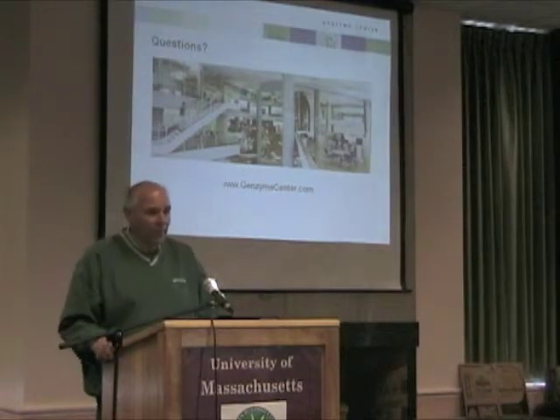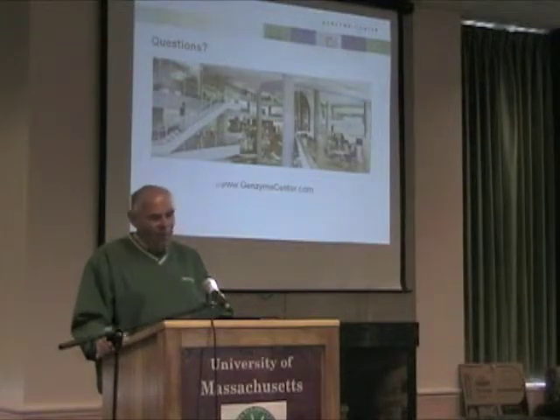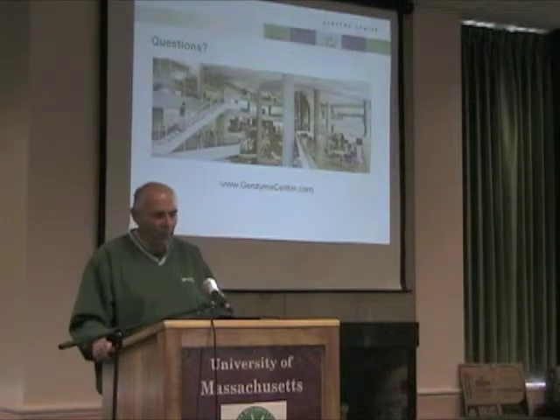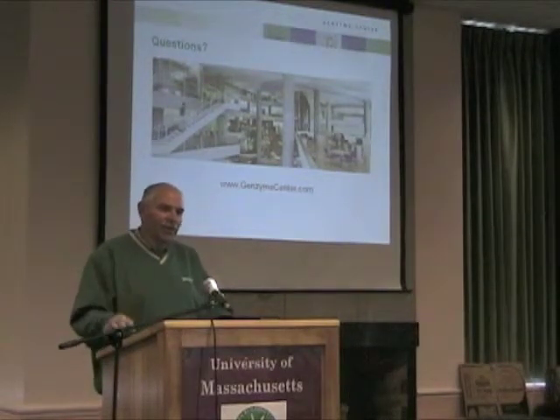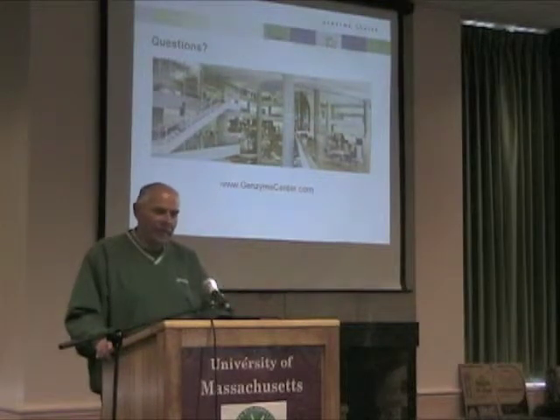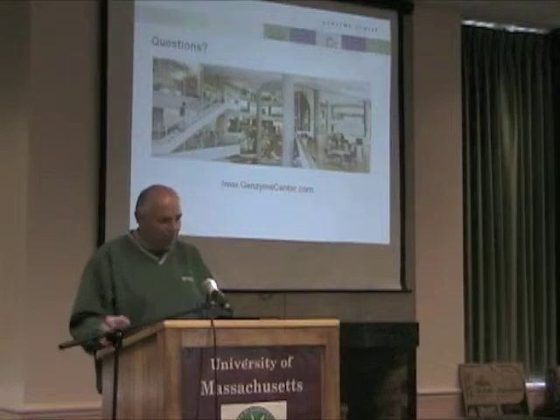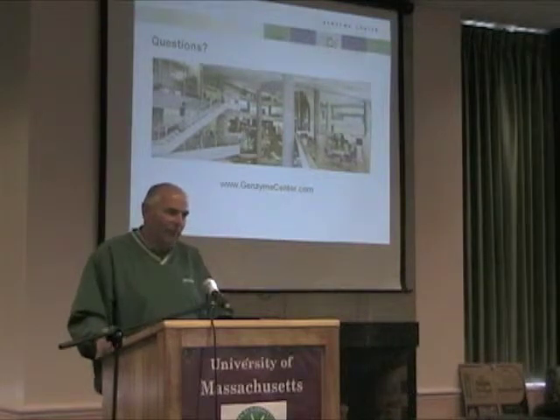I said, well, it's a platinum building. What can you save? We gave them a month. They came back and said the most we can save is maybe $40,000, $45,000, maybe a little bit more. And I said, well, I'll tell you what, what do you think we can do? He says, well, we have all these ideas about going to the deadband, going this and that. So you just tell me what you want to do, and we'll do it with our programming on our BMS. By the time we got done, we saved almost $195,000 a year.